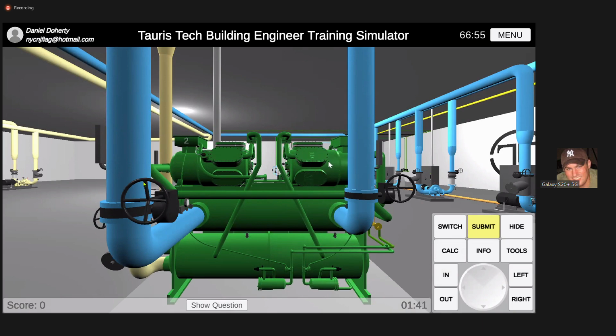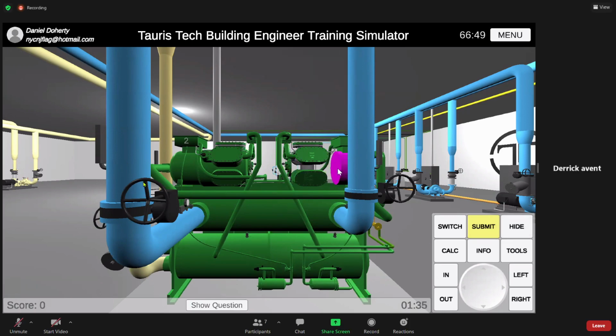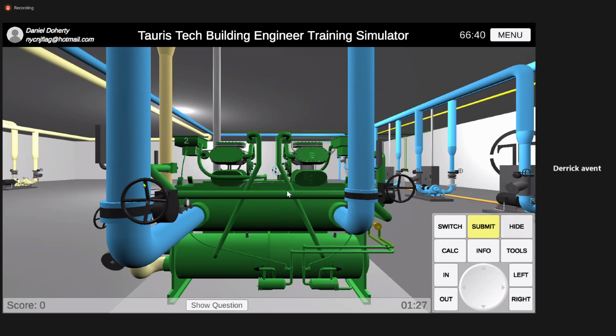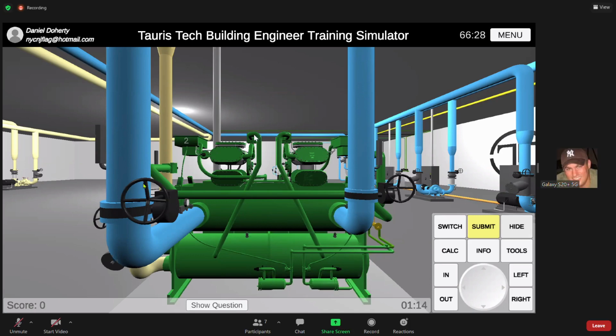What's this? The compressor. What's that? The compressor, yeah. So what's this? The motor. Oh, that's the motor, compressor. Okay, what's this line right here? That's the hot line, discharge. Superheated vapor, yeah, you gotta remember, it's high pressure, high temperature, superheated vapor in your discharge line.